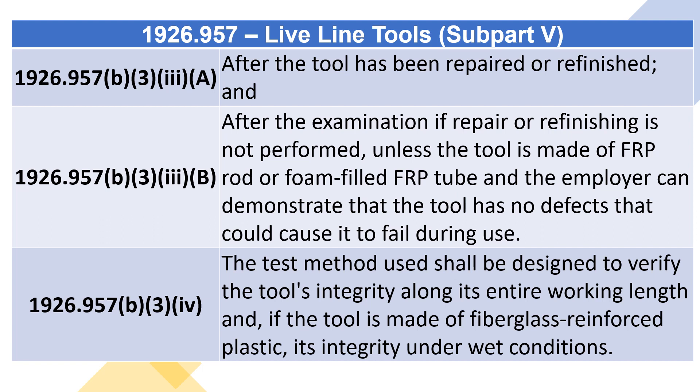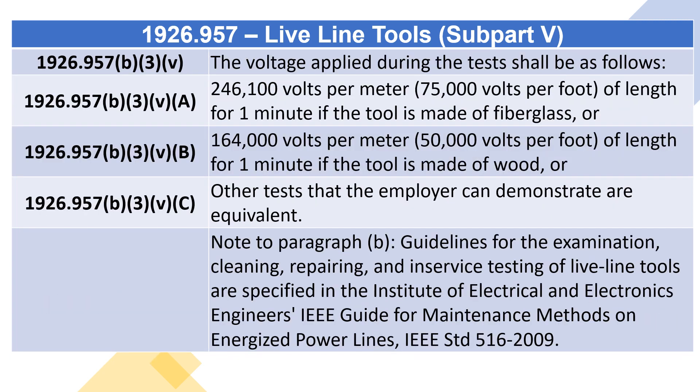1926.957(B)(3)(iv): The test method used shall be designed to verify the tool's integrity along its entire working length, and, if the tool is made of fiberglass-reinforced plastic, its integrity under wet conditions. 1926.957(B)(3)(v): The voltage applied during the tests shall be as follows: 246,100 volts per meter (75,000 volts per foot) of length for one minute if the tool is made of fiberglass, or 164,000 volts per meter (50,000 volts per foot) of length for one minute if the tool is made of wood, or other tests that the employer can demonstrate are equivalent.